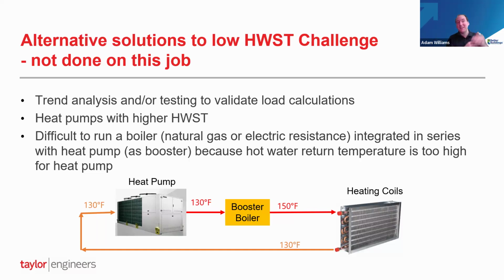curtail their heating capacity and say, oh, you sent us 127-degree water, we'll heat it up to 130-degree hot water and just run one of our compressors, right? Or they'll just trip because the return water temperature is too high. Now your heat pump doesn't really do what it was designed to do, and you're running only on the booster boiler. So this is just something to keep in mind.